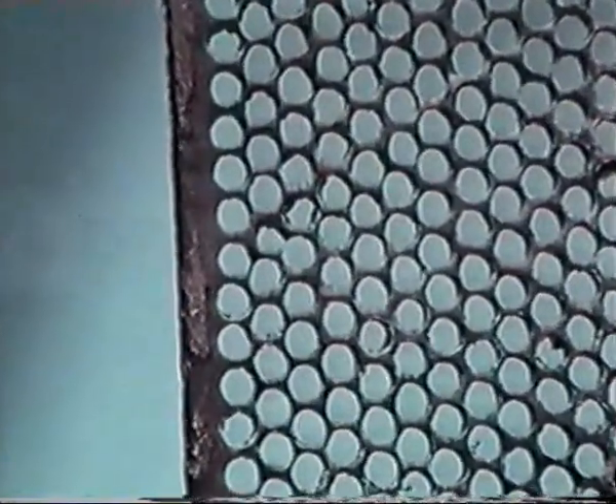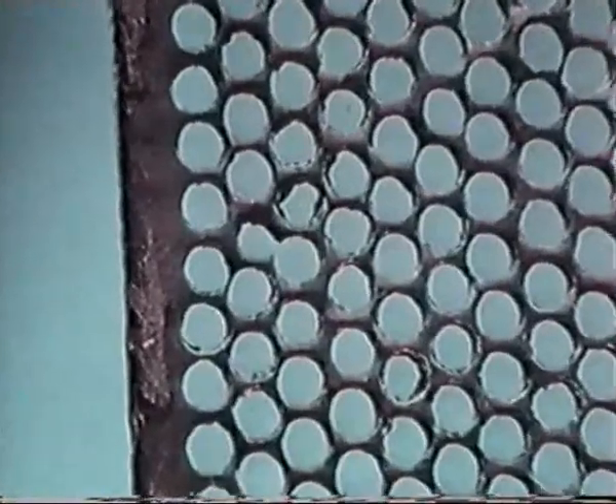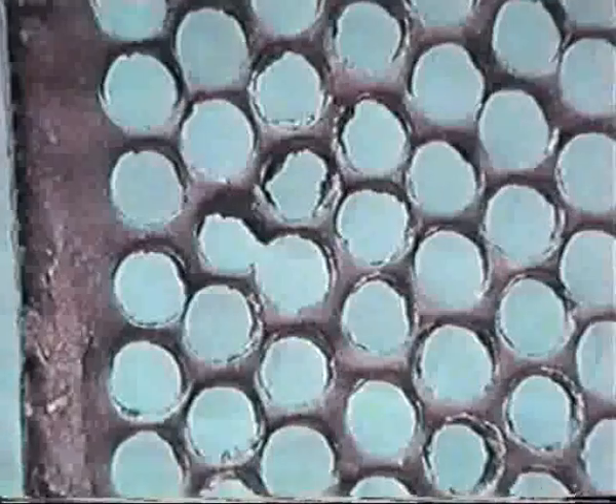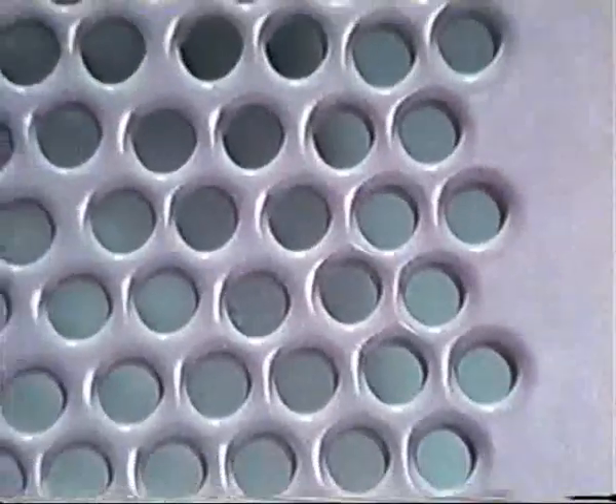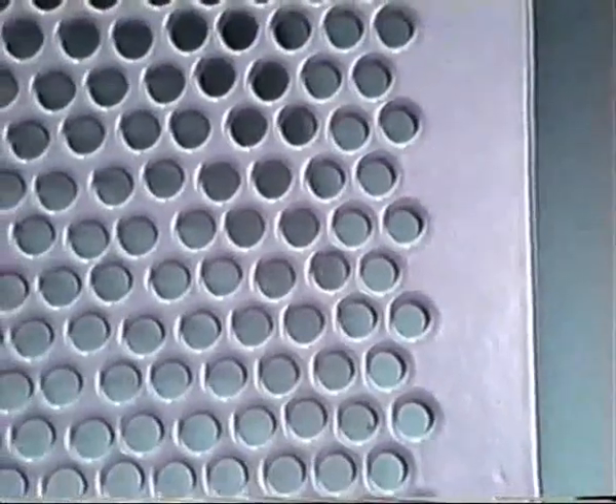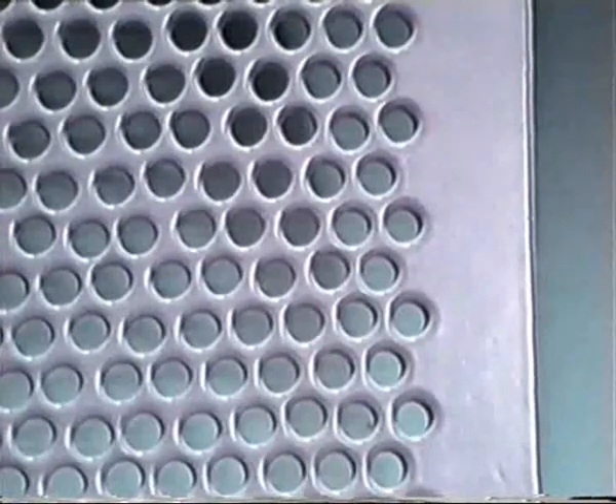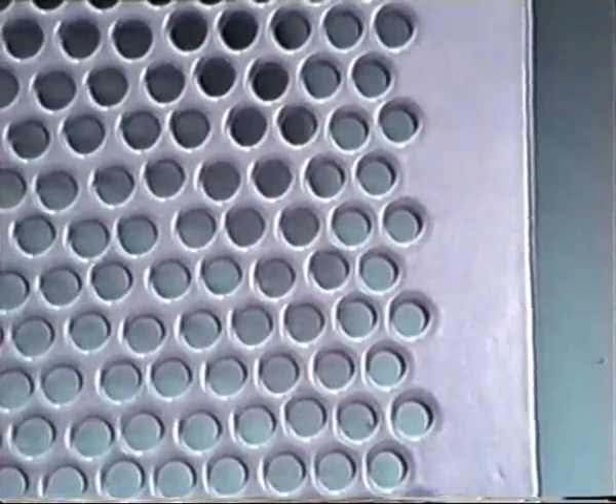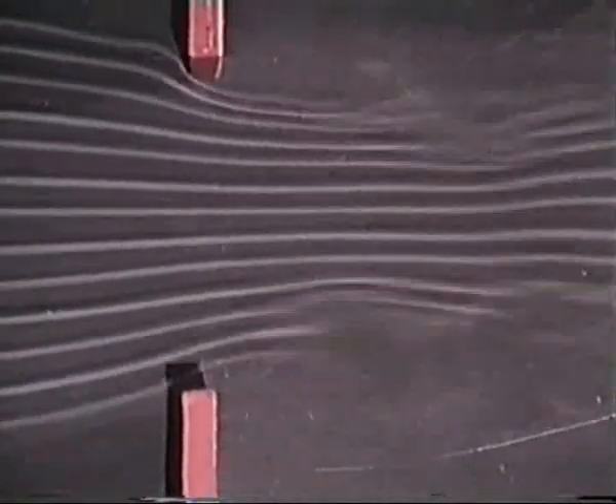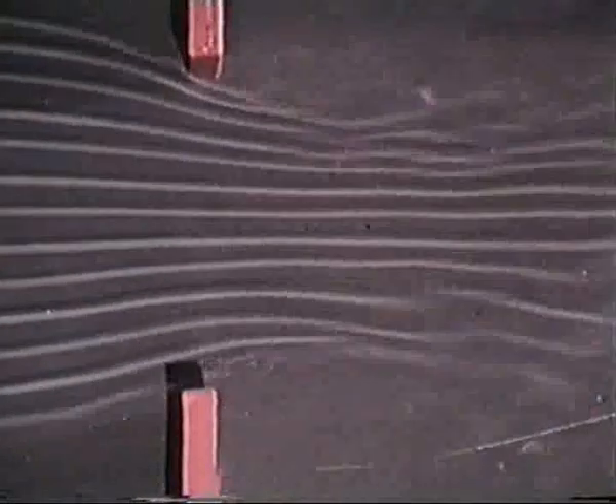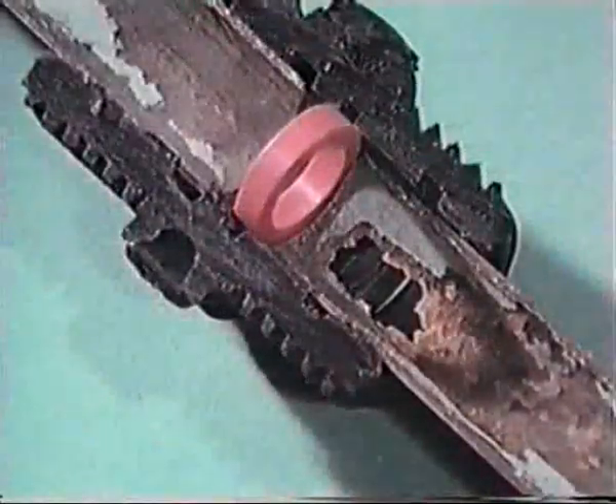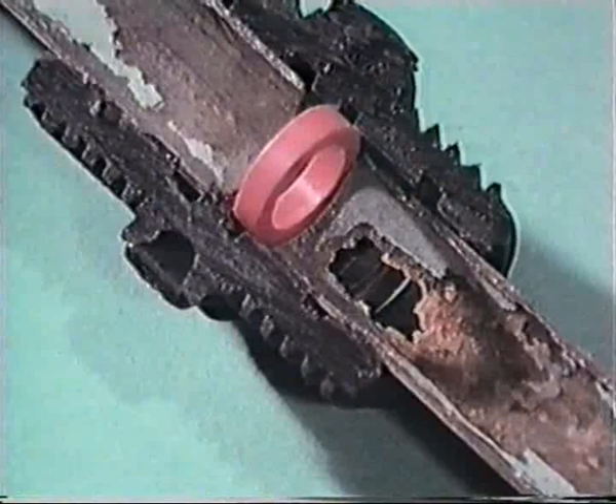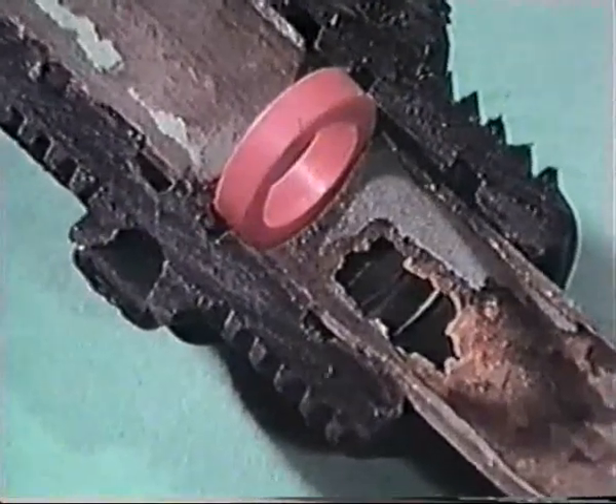A brass filter was similarly corroded because of the speed of flow of seawater. The solution was to use a plastic-coated material inert to seawater, which incidentally was cheaper than brass. Interference with normal flow can lead to turbulence, for example, a protrusion into the stream. A wrongly sized packing gasket caused turbulence and eventually erosion corrosion.